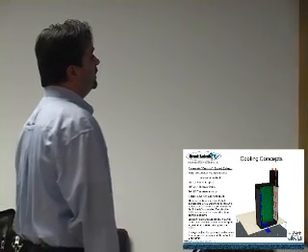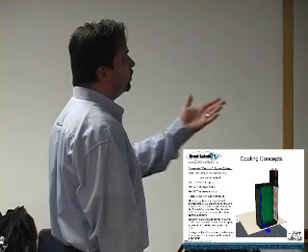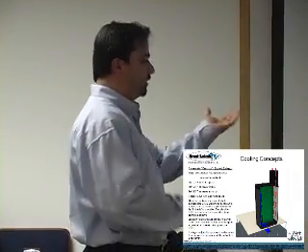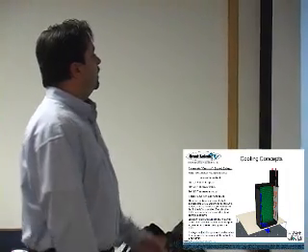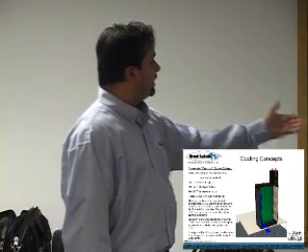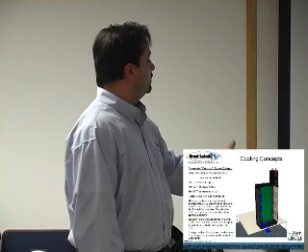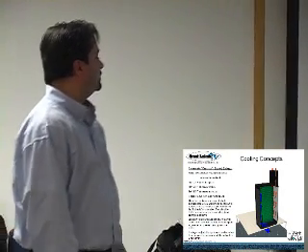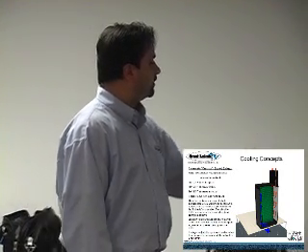We're seeing approximate kilowatt loads of 8 to 12 with this. Some of them are being very conservative here. The return air temp is increased. That's what we said before. Fewer perf tiles are required to cool the white space only. The intake air is forced through an adjustable air diverter directly from the CRAC.